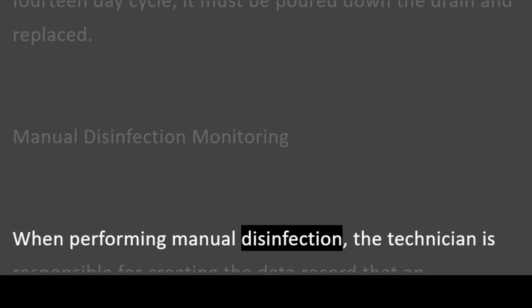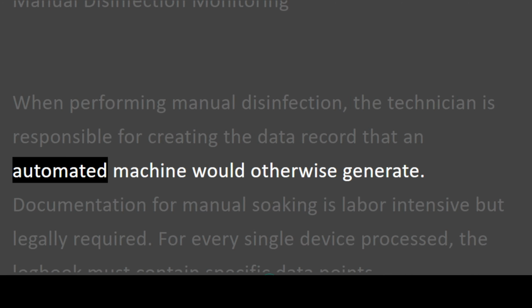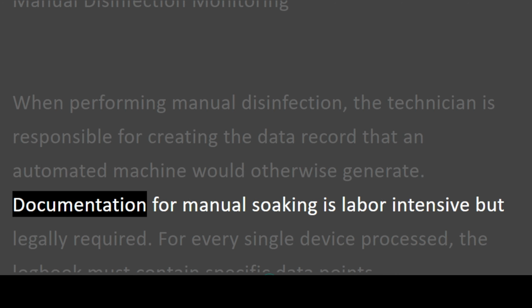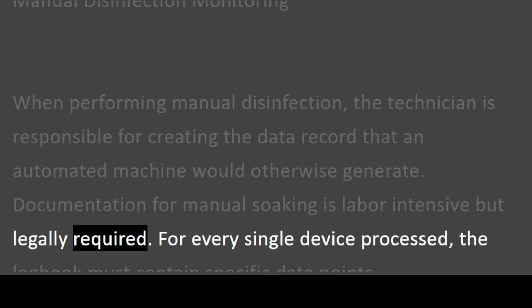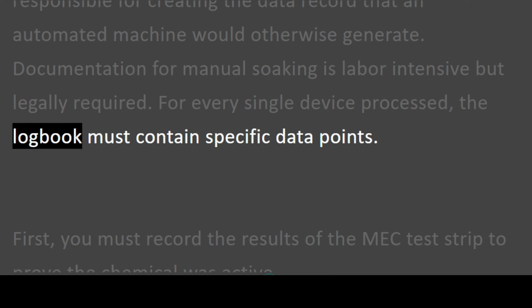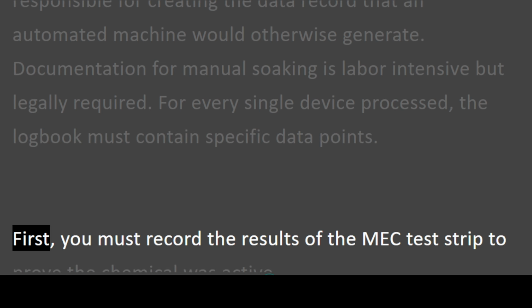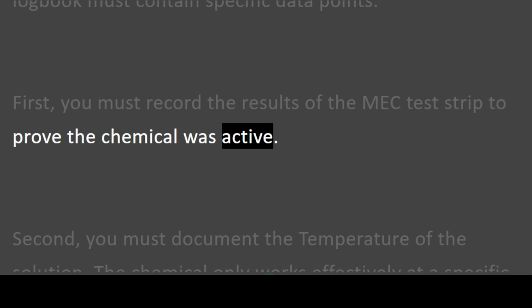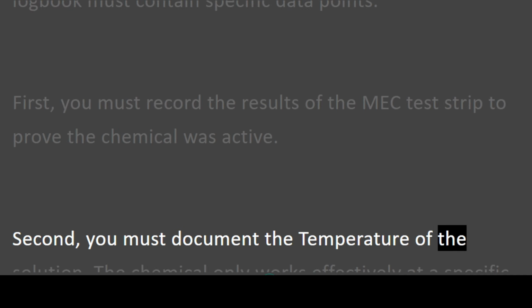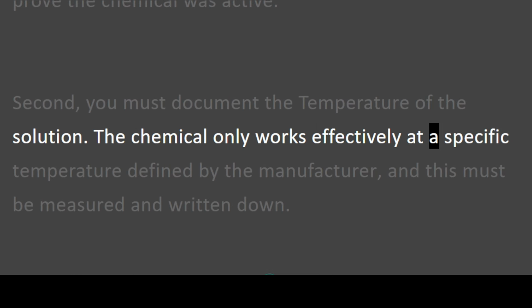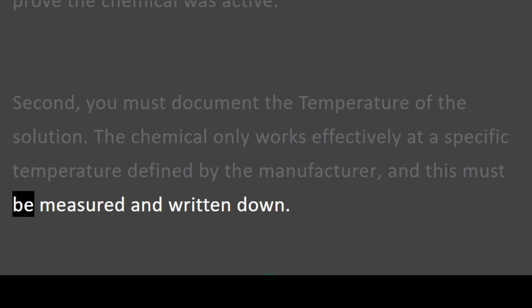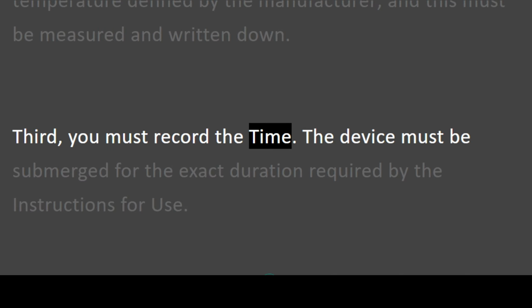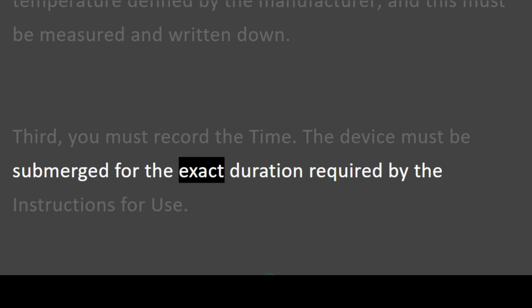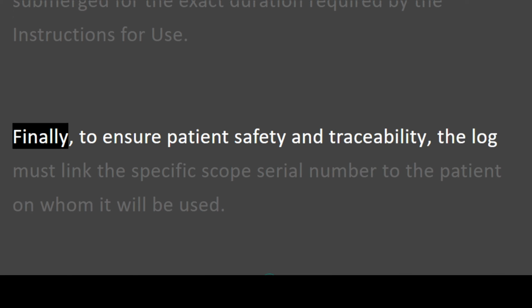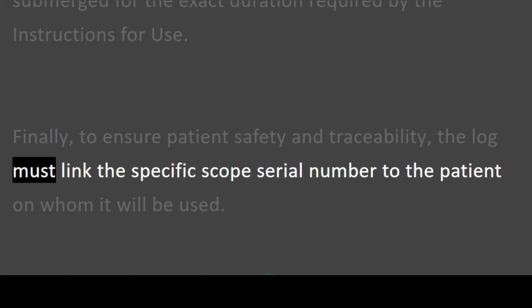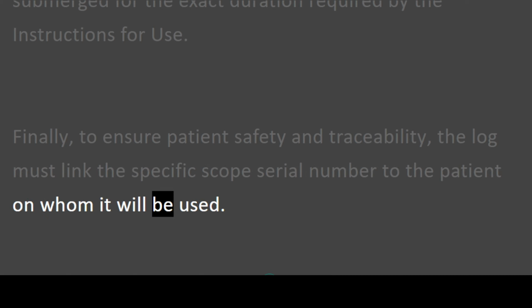Manual disinfection monitoring. When performing manual disinfection, the technician is responsible for creating the data record that an automated machine would otherwise generate. Documentation for manual soaking is labor-intensive but legally required. For every single device processed, the logbook must contain specific data points. First, you must record the results of the MEC test strip to prove the chemical was active. Second, you must document the temperature of the solution. The chemical only works effectively at a specific temperature defined by the manufacturer, and this must be measured and written down. Third, you must record the time. The device must be submerged for the exact duration required by the instructions for use. Finally, to ensure patient safety and traceability, the log must link the specific scope serial number to the patient on whom it will be used.